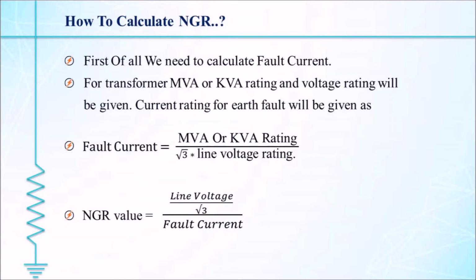First of all, we need to calculate the fault current. To find the fault current of the transformer, the transformer MVA or kVA rating and voltage rating will be given. Then the following formula gives the current rating for the earth fault, that is, the fault current is equal to MVA or kVA rating divided by root 3 into line voltage. From this value of the fault current, the value of NGR can be calculated as given below. NGR is equal to line voltage divided by root 3, whole divided by fault current.